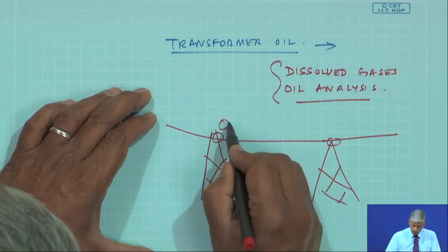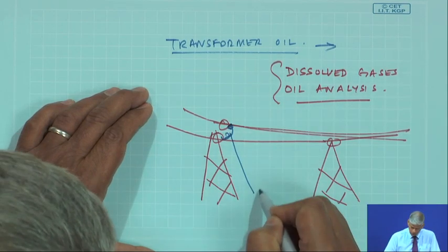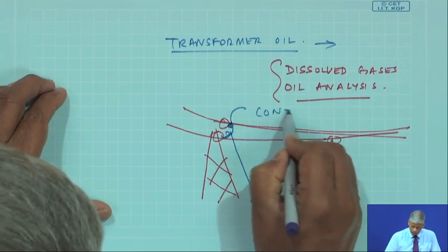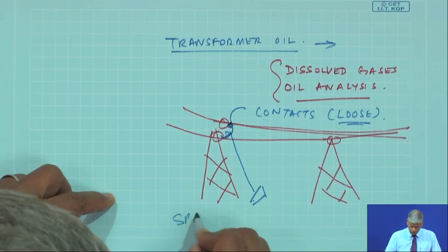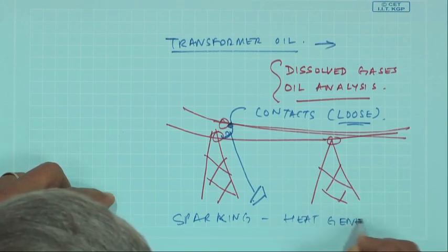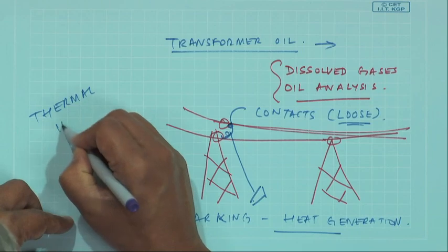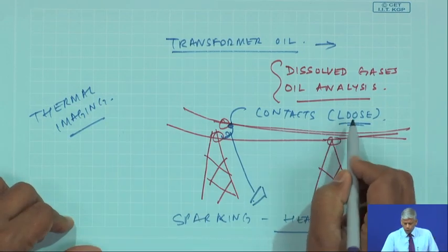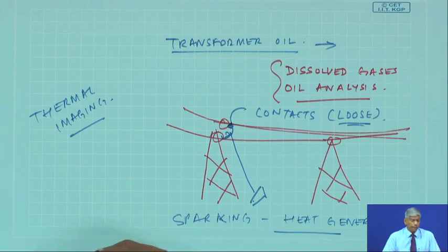For switchgear — current-carrying conductors where connections and contact points exist — loose contacts create sparking and heat generation. Through thermal imaging, such loose contacts can be identified. This will be discussed further when we cover thermography in the next lecture. More on MCSA can be found in the referenced book and website. Thank you.